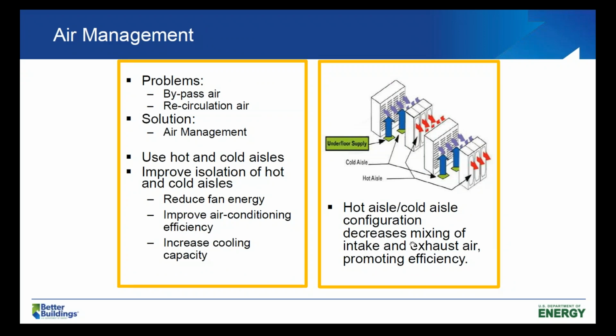So the problems of air management that need to be dealt with are air going where you don't want it and not where you do want it. And that's the basic problem of air management. It simply means forcing the cool air to go where it's needed and preventing it from mixing with the hot air. So we have problems of bypass air and recirculation air, and the solution is better air management.